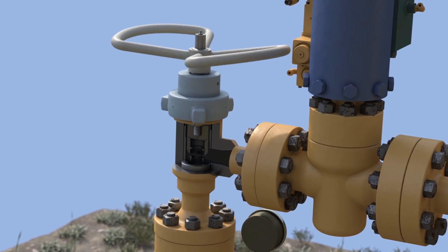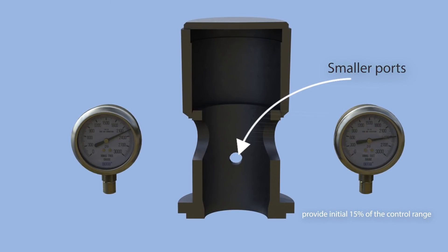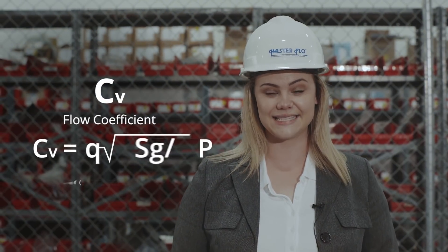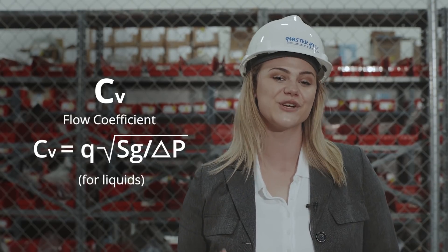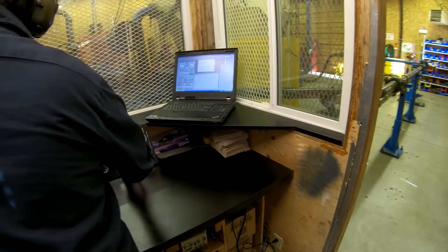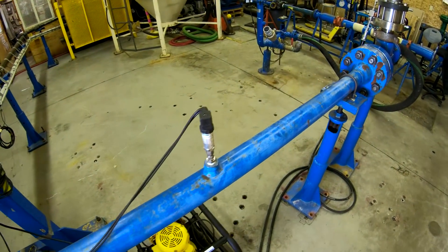Master Flo's standard trim provides a high level of control over its life. The smaller, lower ports provide the initial 15% of the control range, while the larger ports provide the valve's overall capacity. This results in an equal percentage flow characteristic curve and high liquid pressure recovery factor. Flow capacity testing establishes a flow curve over the valve travel and provides a basis for comparing trim styles. Each valve type has a unique curve based on internal geometry.